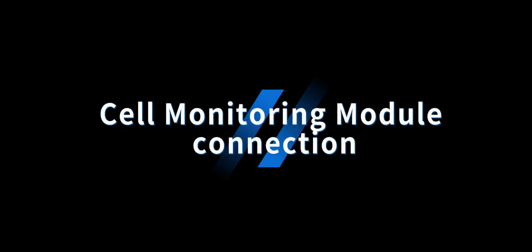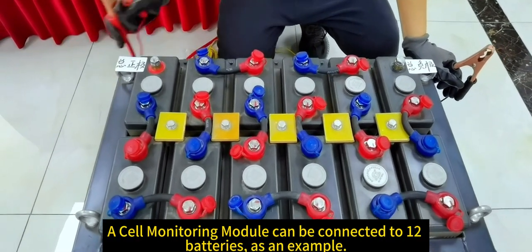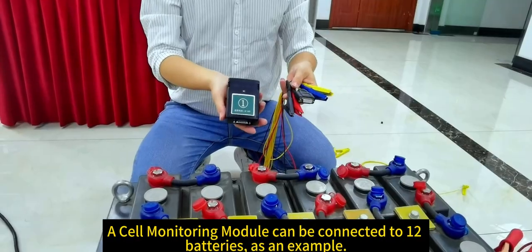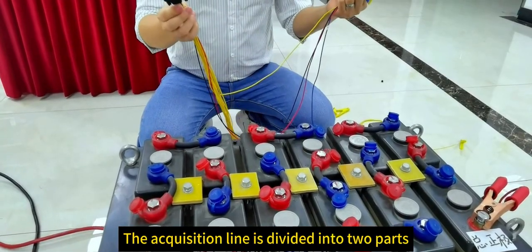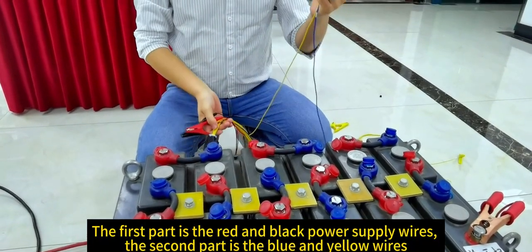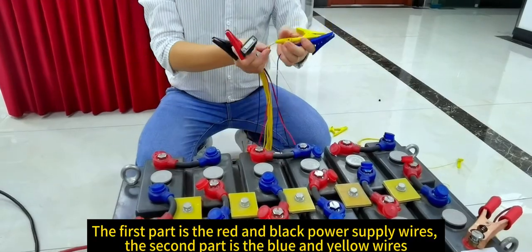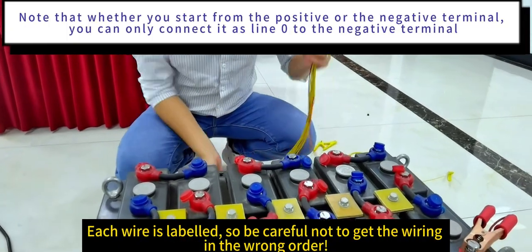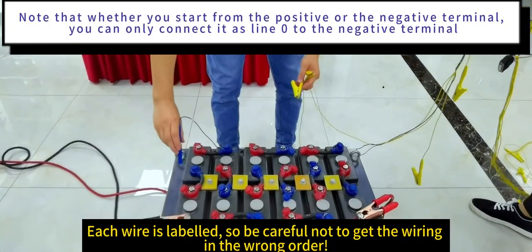Cell monitoring module connection. A cell monitoring module can be connected to 12 batteries. As an example, the acquisition line is divided into two parts. The first part is the red and black power supply wires. The second part is the blue and yellow wires. Each wire is labeled, so be careful not to get the wiring in the wrong order.